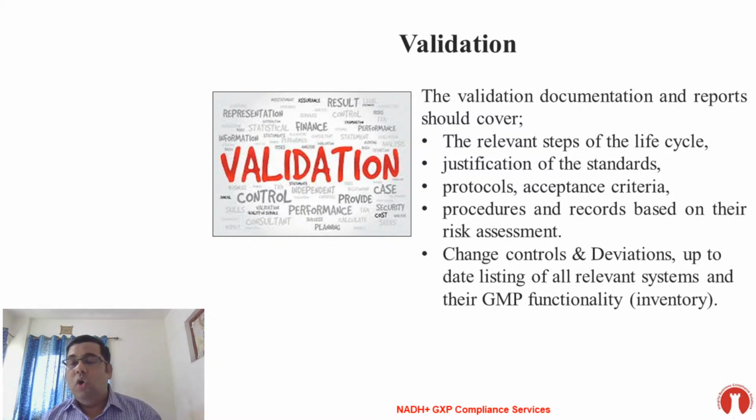Considering all this background, my suggestion is, okay, the vendor is giving you quality risk management, no problem, but that quality risk management should be reviewed and evaluated, whether it is up to the mark or not. If not, then you should raise an addendum, and in the addendum you have to identify further risks, and those risks should also be addressed, and a further mitigation plan should be taken, either automated. If it is a bespoke system, you can tell the supplier that you want these controls added. If it is off the shelf, then you have to put in manual controls to ensure compliance with the requirements.